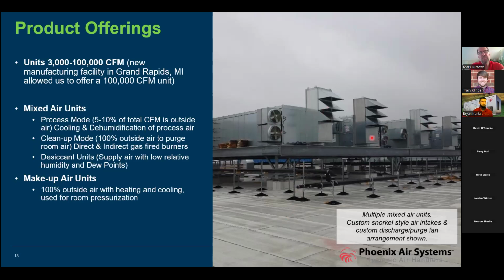And just before you flip the switch on this, we did a job once at a different company where I worked. Not only is it critical where these units are placed as far as air distribution in the plant, this job was in Manitoba. It was -40 without the wind chill. They had units very close like this. When they went in the sanitation cycle, out of the discharge, and typically those exhaust fans are perpendicular to the unit. You can see these are canted 45 degrees, so the air does not smash into the next unit. Well, imagine when it's -40 degrees outside and you've got discharge air at 75 degrees full of moisture. It basically made that next unit an igloo.